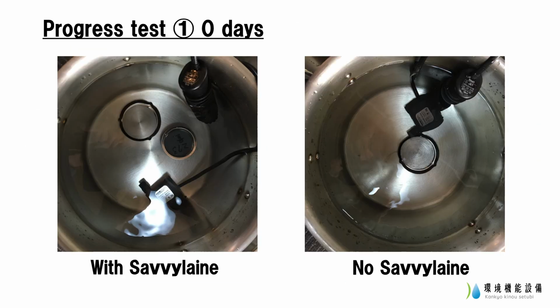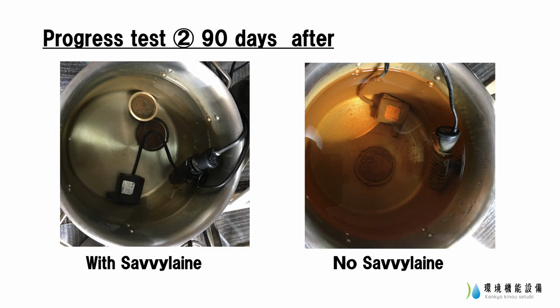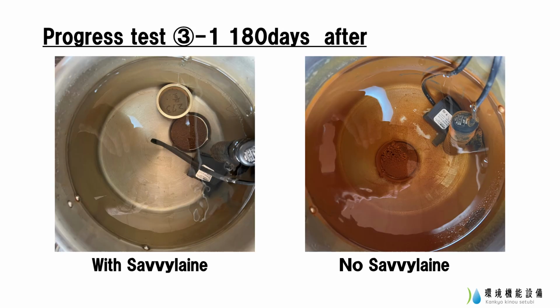These are test images of SAVVY-LAINE. S45C iron pieces were placed in both tanks, with SAVVY-LAINE on the left and without on the right. This is a picture from the start. 3 months have passed, and the right side is badly rusted. 6 months have passed. You can see that there is a lot of rust in the tank on the right, but although you can see rust on the iron pieces on the left, the water is still very clear. Normally, this would be the time to clean and change the water.